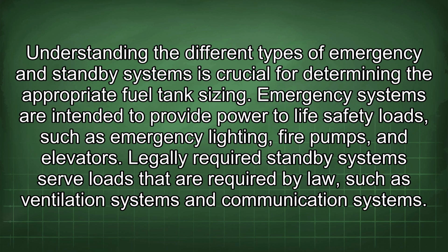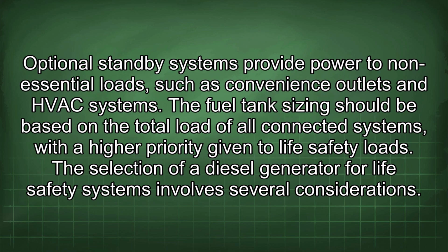Emergency systems are intended to provide power to life safety loads, such as emergency lighting, fire pumps, and elevators. Legally required standby systems serve loads that are required by law, such as ventilation systems and communication systems. Optional standby systems provide power to non-essential loads, such as convenience outlets and HVAC systems. Fuel tank sizing should be based on the total load of all connected systems, with a higher priority given to life safety loads. The selection of a diesel generator for life safety systems involves several considerations.